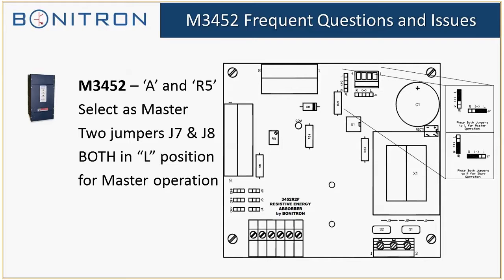The reason we don't automatically ship them as master units is because if they were to place two or more masters together on a common bus, then we just can't predict their interaction. The interaction will be chaotic, and one M3452 might end up destroying the other, basically because they can get into a fault state of basically rapid switching. So that's why if customers order two or more units of M3452s, they're all set for slave operation.